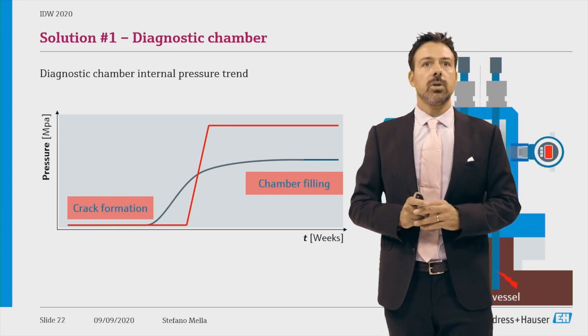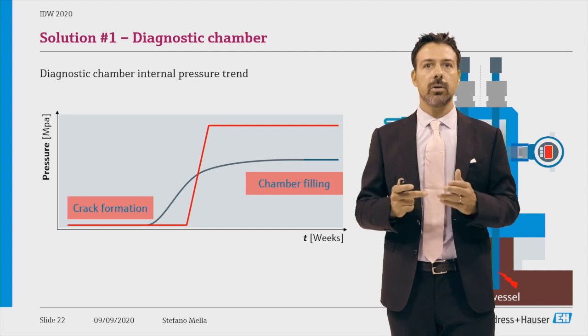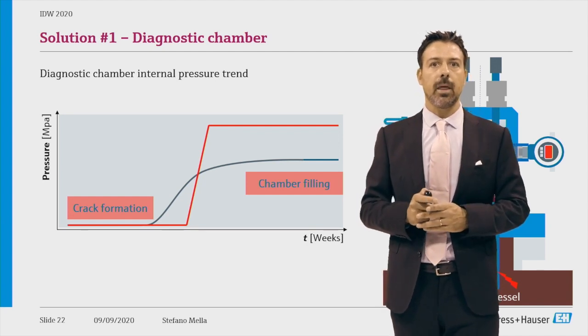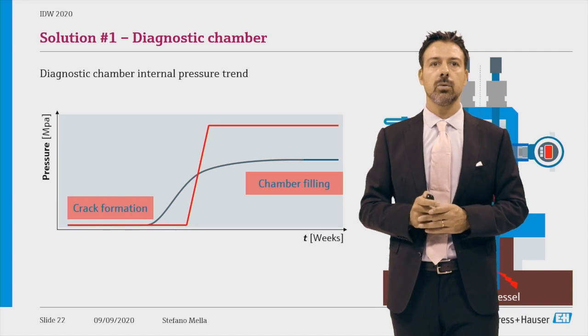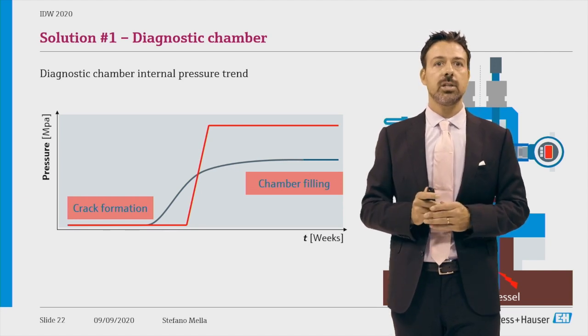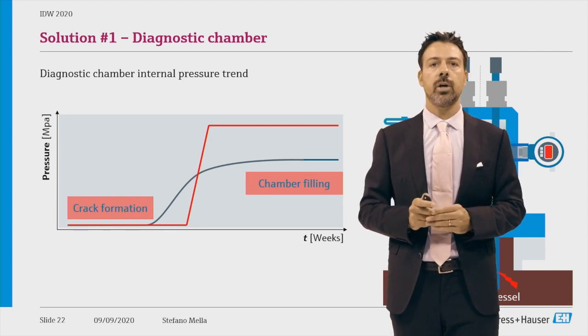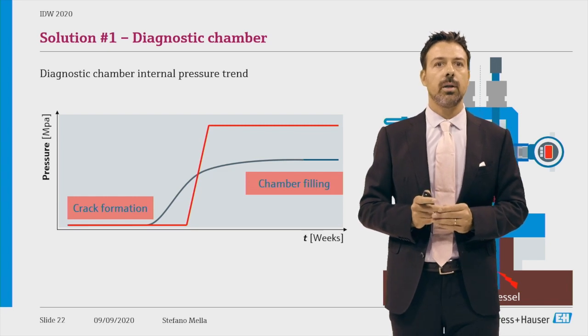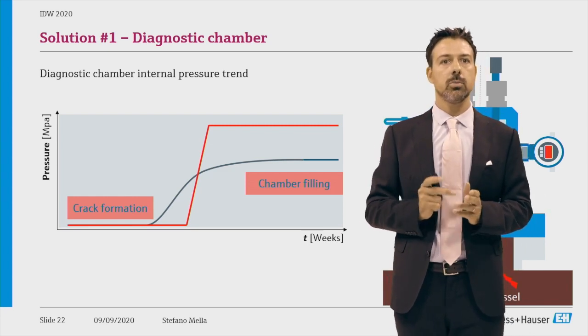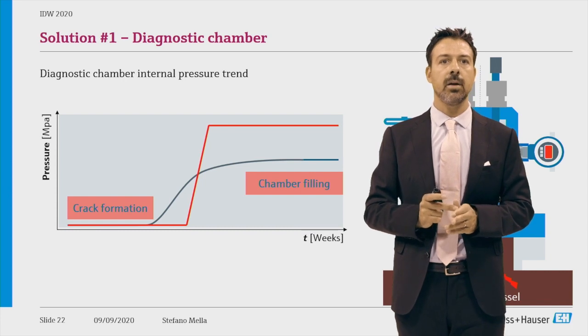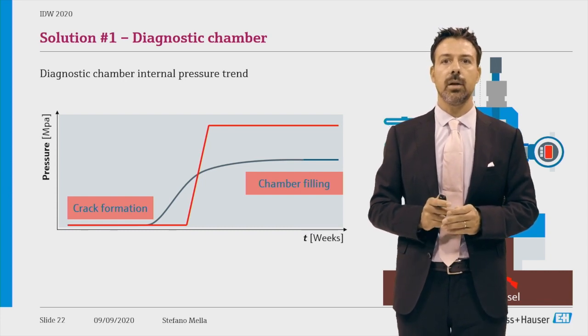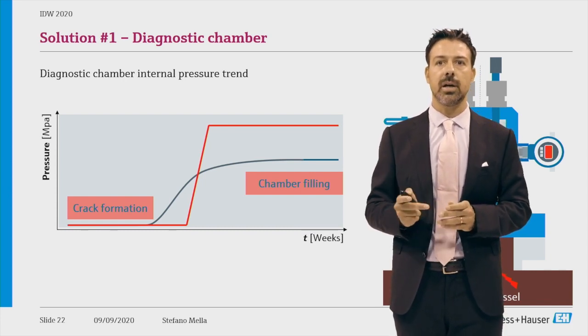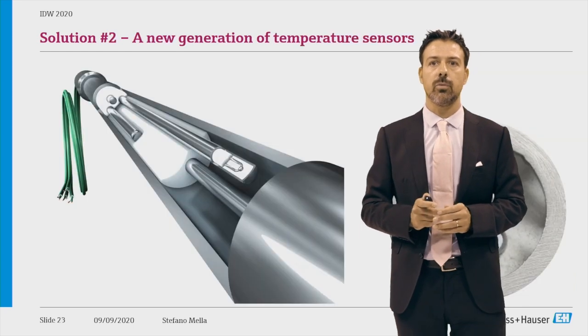The question before was, okay, and how can I recognize a drift and how can I take it into consideration? First suggestion is if you have overpressure inside the diagnostic chamber, then your measuring points are no longer to be trusted because, as I explained, it's only a matter of time until the reading is lost entirely or it shows a wrong value.